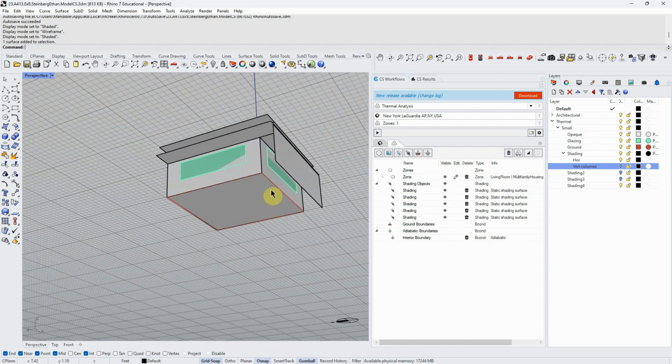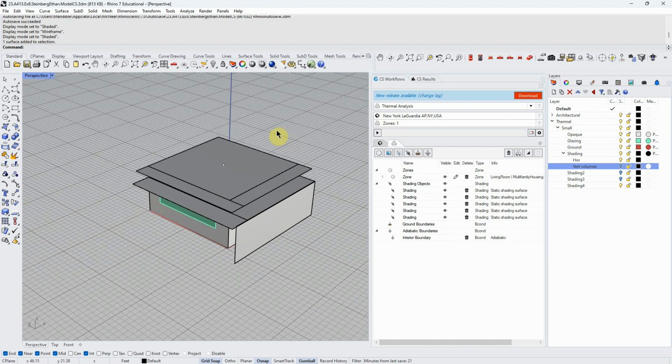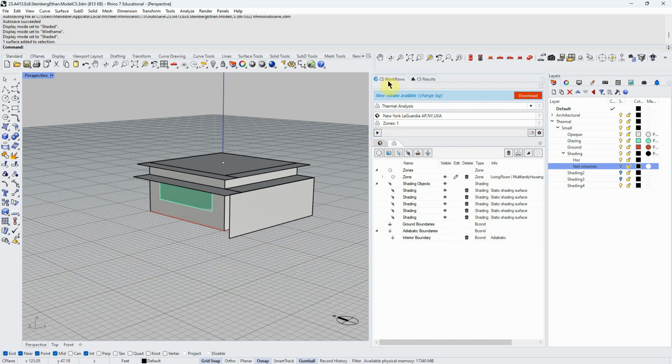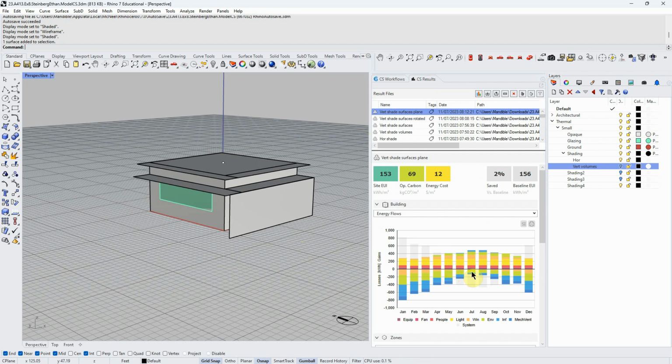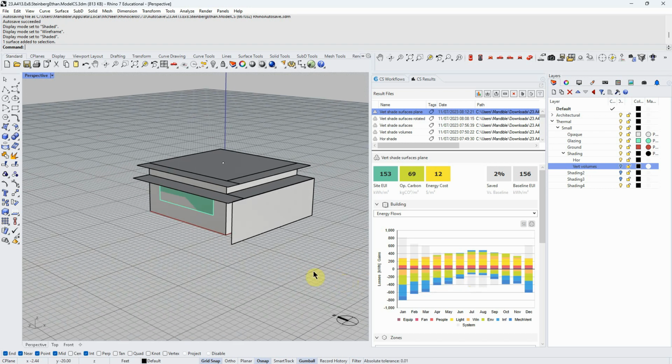Your ground condition is completely different than that. There's definitely heat loss through the ground, but it is going to be different than heat loss through the air because it's a different physical environment. And there are definitely things I wanted you to look at there, because you would learn something. We would be looking at the winter months in terms of heat loss into the ground as compared to the summer. And if we're losing more heat into the ground in the summer, it's possible that we would not want to insulate underneath the ground. So it'd be about checking our envelope down the road and playing around with insulation levels and deciding if we wanted to insulate or not based on these outputs.